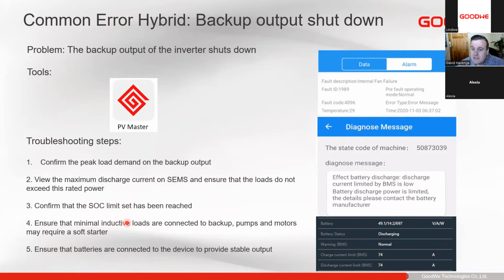Next, we also have to look at inductive loads. Unfortunately, inductive loads are an inverter's worst enemy. Inductive loads can draw anywhere from 3 to 12 times the rated power output on startup, based on the age of the load. Fridges, freezers, newer ones, you have very little problem with. As they age, as capacitors get older on the devices, the windings get older, the current draw on startup generally increases greatly, and those can overload inverters in an off-grid scenario.